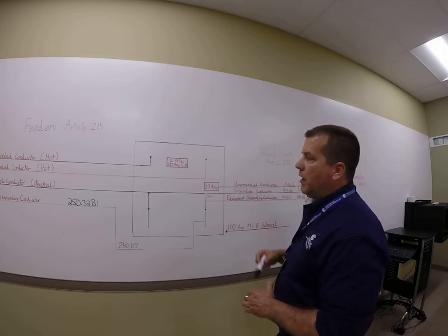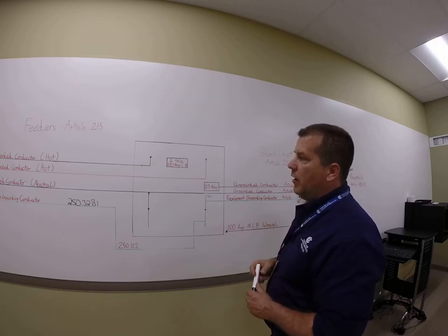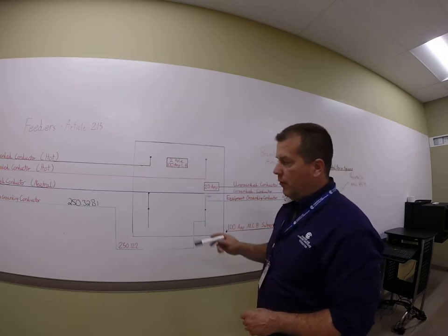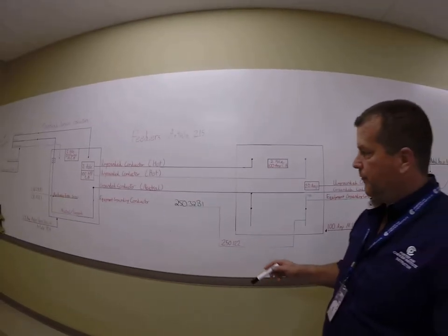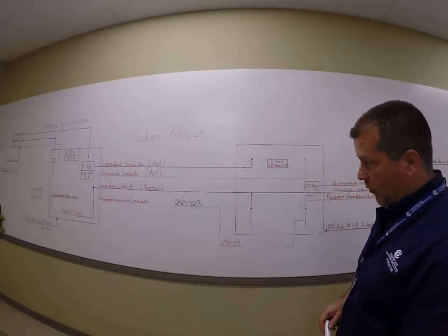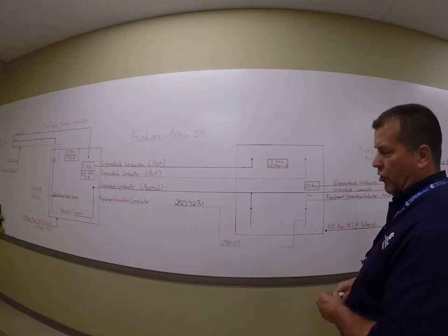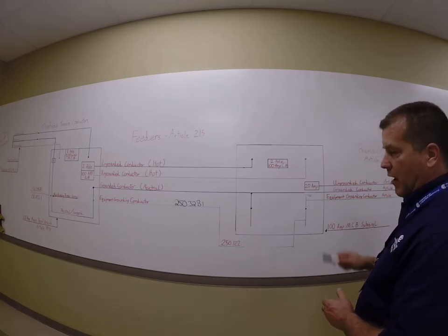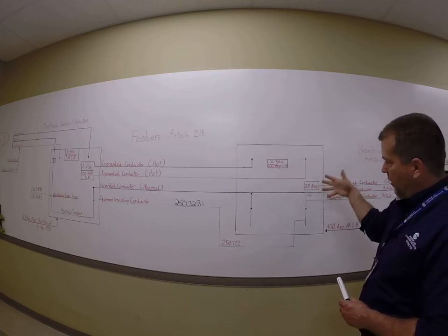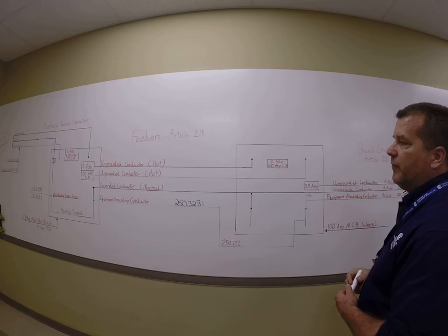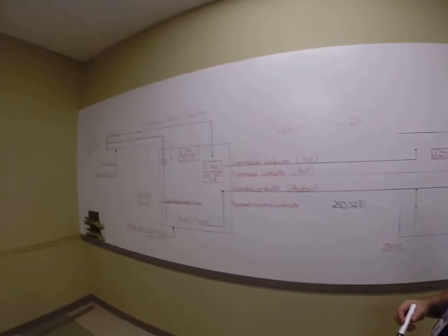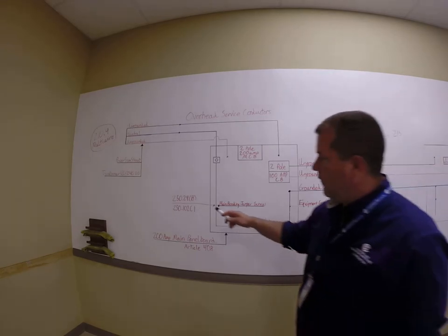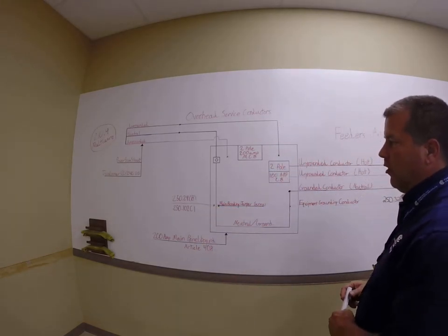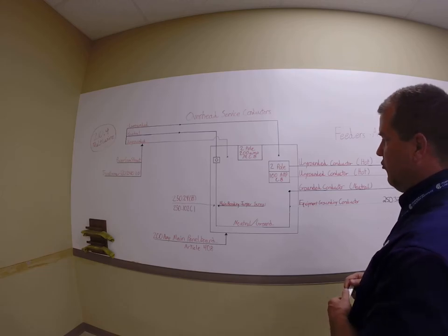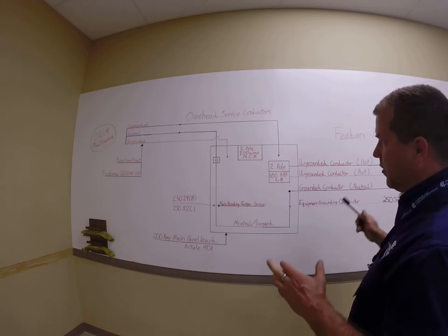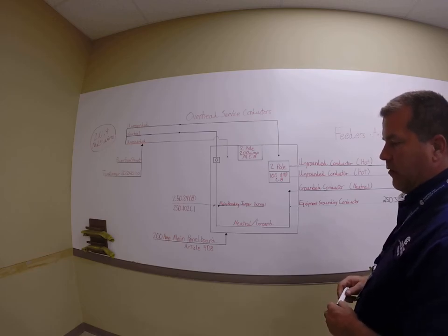So once again, everything we touch goes back to the code book. I'm going to zoom around and show you some code articles in here, but the important one in the code book is 250.32(B)(1). When you read that, it's language that's hard to understand, but basically they're saying, and I'll bring it up in the code book, that this has to be isolated. These cannot touch. The other code article that says where they're supposed to touch is 250.24(B). 250.102(C)(1) shows us how to size that main bonding jumper. But there's more to it than this, and the important thing is you want to get it right.